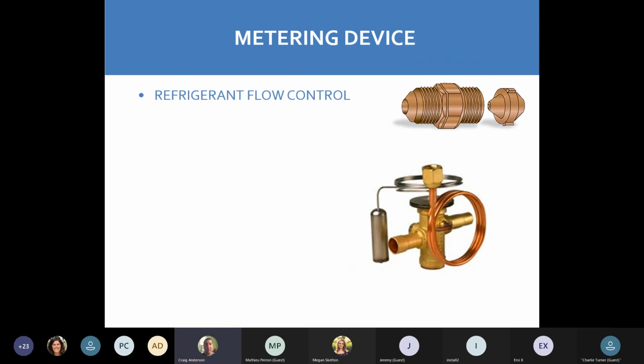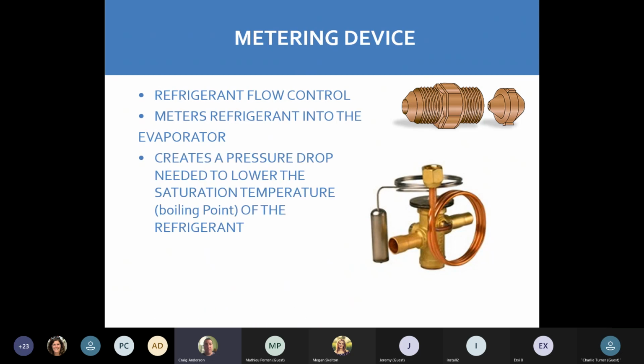So metering device, refrigerant flow control, that's what it's doing. Meters refrigerant into the evaporator coil, whether it's through a piston or whether it's through a TX. Creates a pressure drop needed to lower the saturation temperature, the boiling point of the refrigerant. So when it hits the coil, it's changing state. So two basic types. The top one, we have our piston that's inside our coil, or we have a TX valve inside our coil. If you're working on heat pumps, they're generally going to have a TX inside, but be mindful of some heat pumps that are outside. Some heat pumps outside will be metered through a piston, and some will be metered through a TX valve as well. So be mindful of what's in each outdoor and indoor unit when you're doing your test.